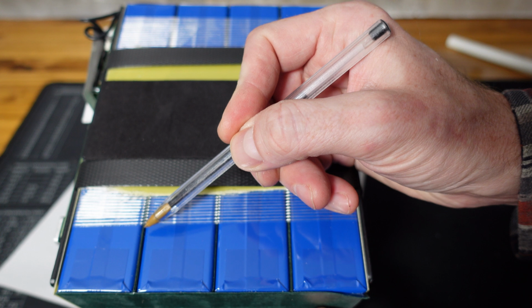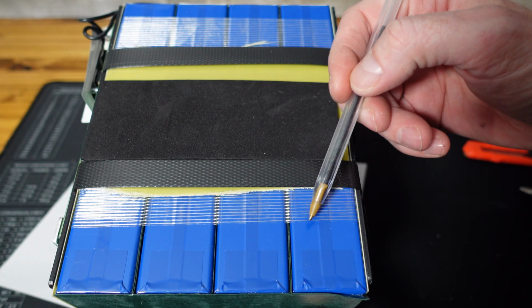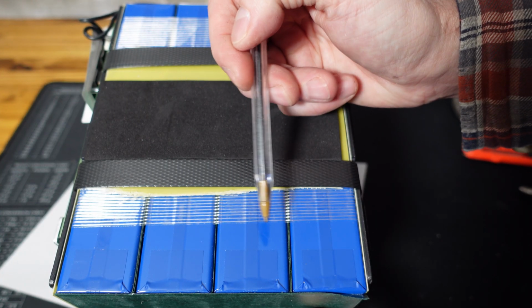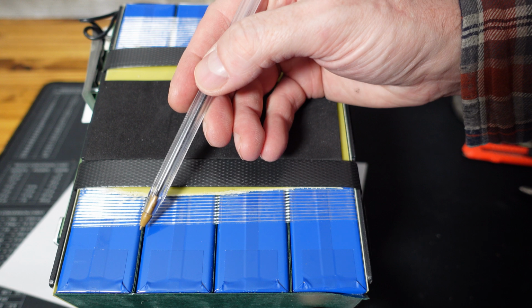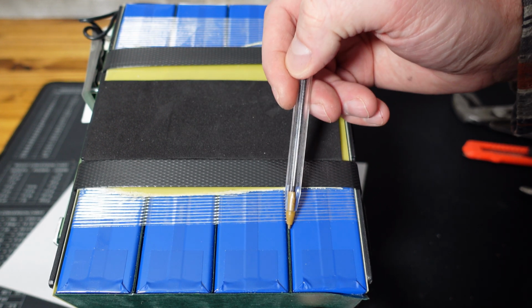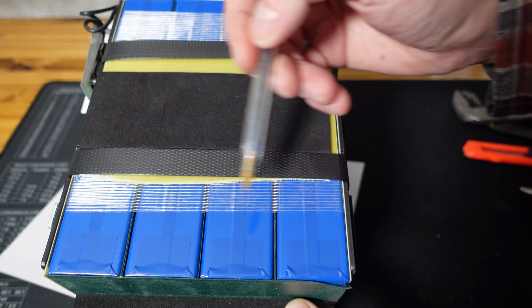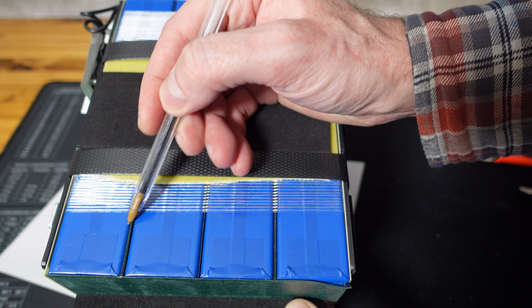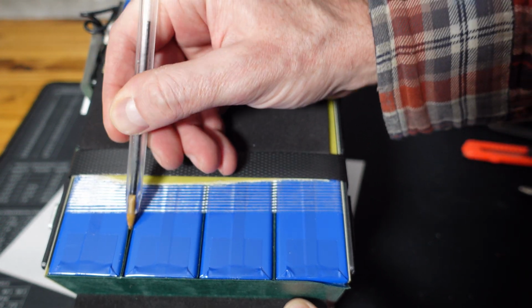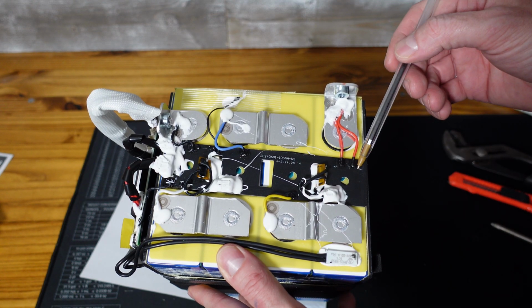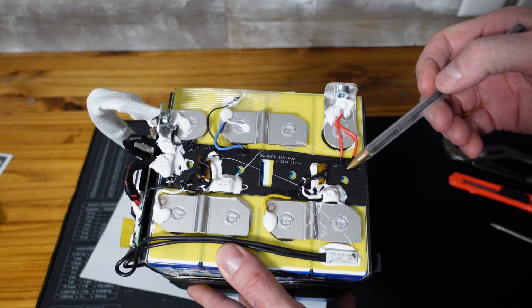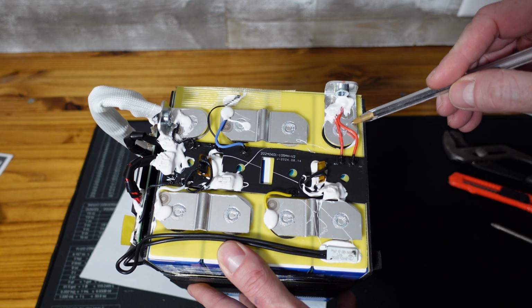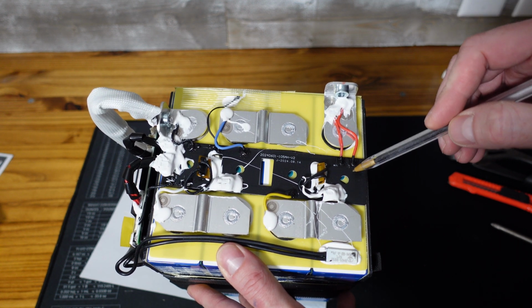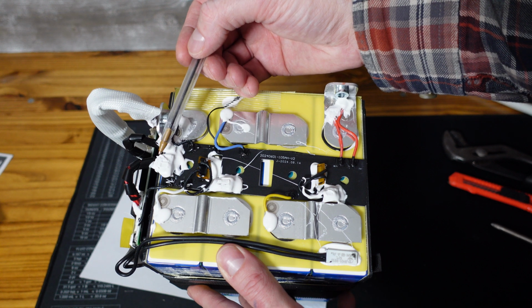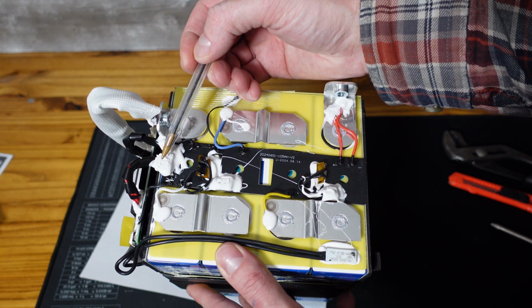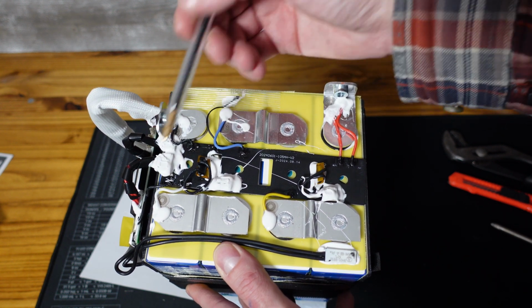Taking a closer look at cells 1 and 2 and 3 and 4, well, all of the cells have this fish paper separator between them. So you can see two layers here, one layer here, and two layers here. On cells 1 and 2 and 3 and 4, we're going to have two layers because between those is the heater pad. One other thing to note about the top of this battery is they are using a PCB approach. While they do have individual balance leads to the terminals, those balance leads come back to the PCB, then they're routed up to a central point here on the left, where there's just a small jumper connector from this PCB over to the BMS.